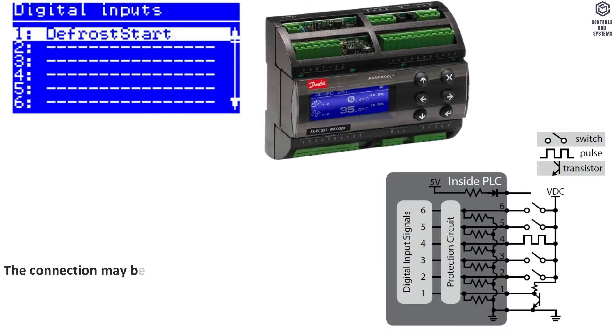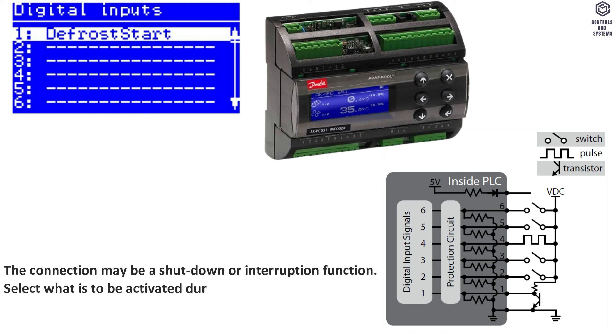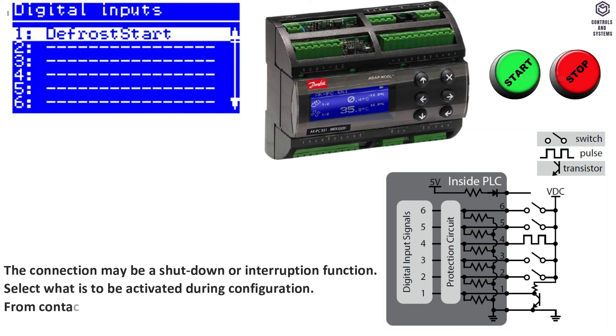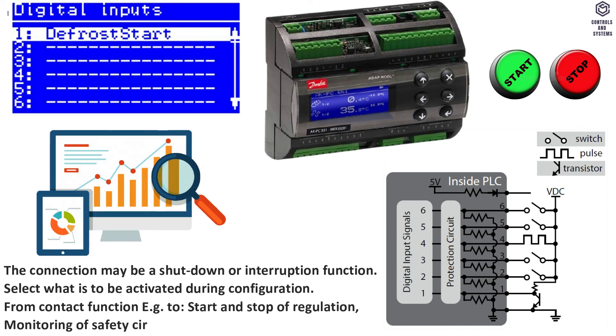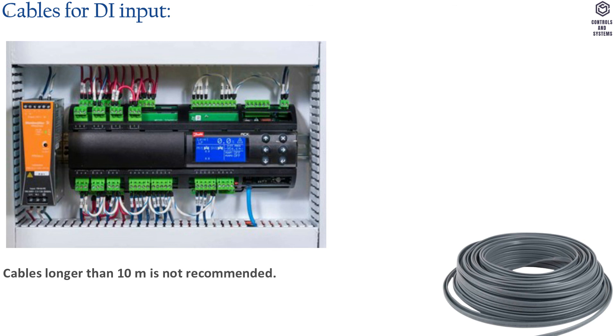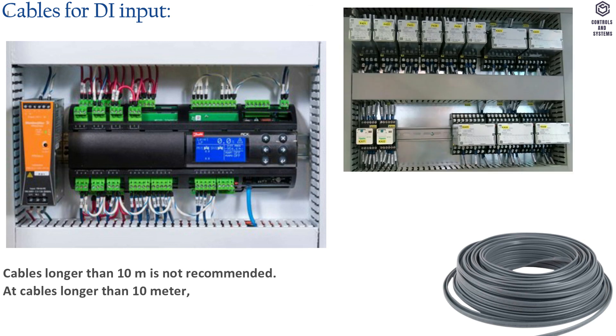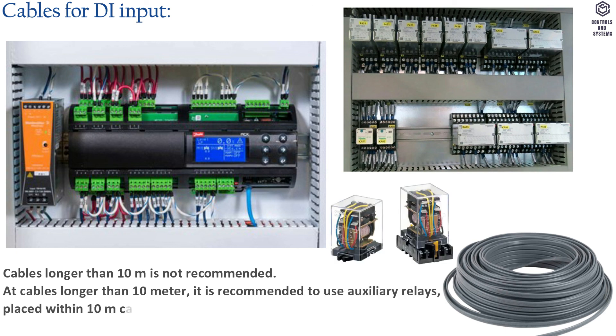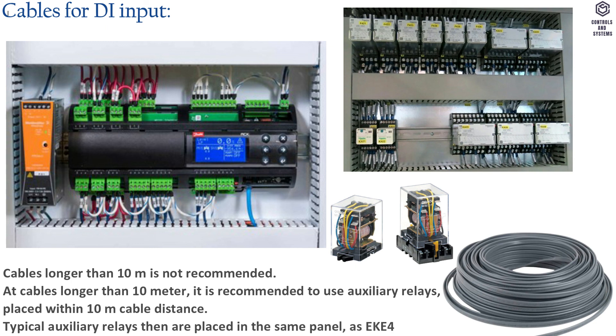Digital inputs: the connection may be a shutdown or interruption function — select what is to be activated during configuration. Contact functions include start and stop of regulation, monitoring of safety circuits, and general alarm function. For DI input cables, cables longer than 10 meters are not recommended. If cables longer than 10 meters are required, it is recommended to use auxiliary relays placed within 10 meters cable distance — typically placed in the same panel as the EKE400.